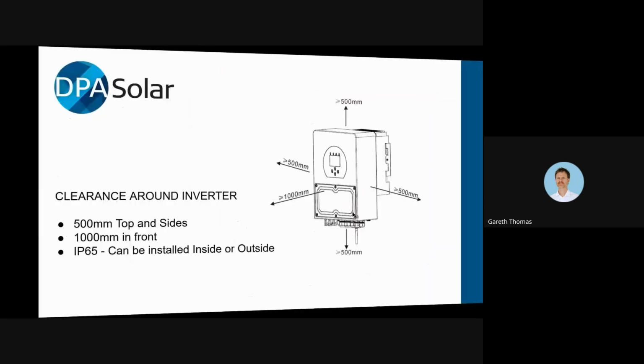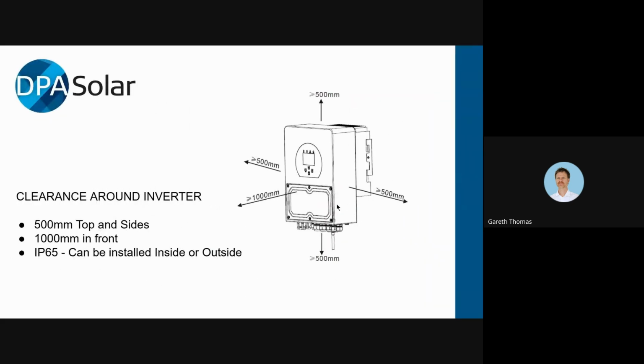In terms of where you can install this inverter, the clearances around it are 500 millimeters top, bottom, and to the sides, and then 1,000 millimeters clearance in front of it. It's an IP65 rated inverter, so you can install it inside or outside, which is great, makes things nice and flexible.